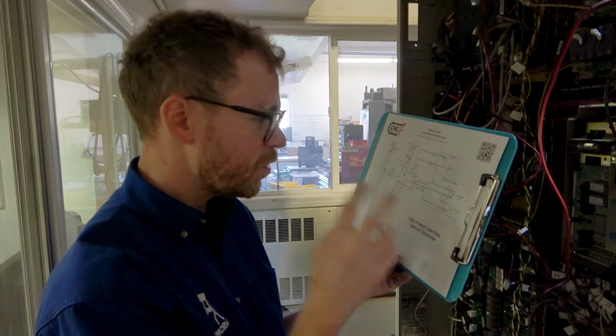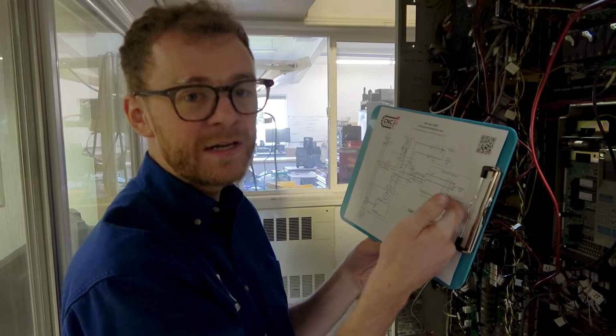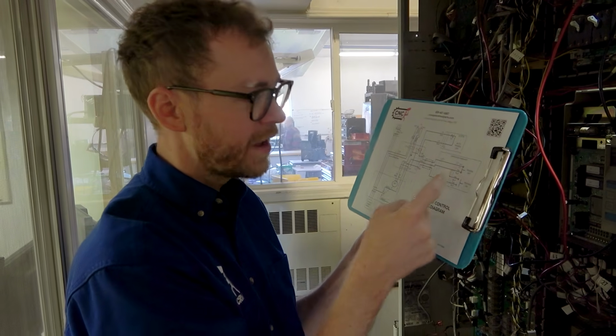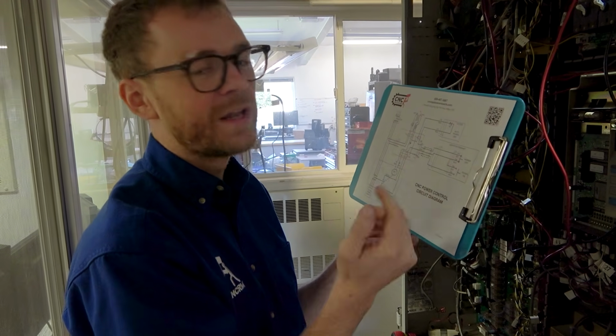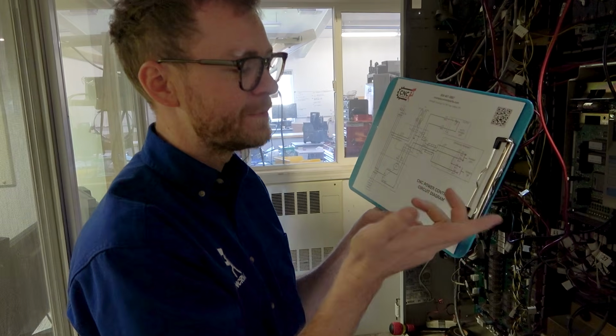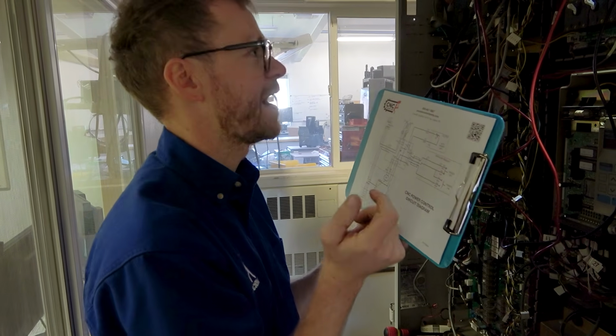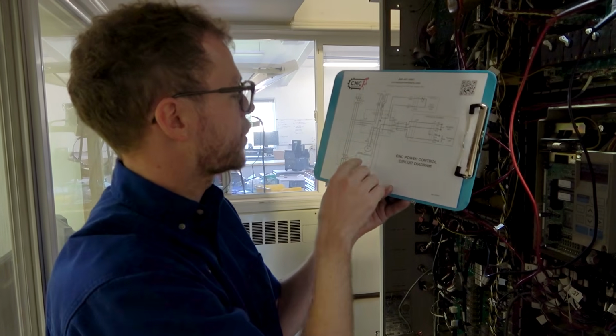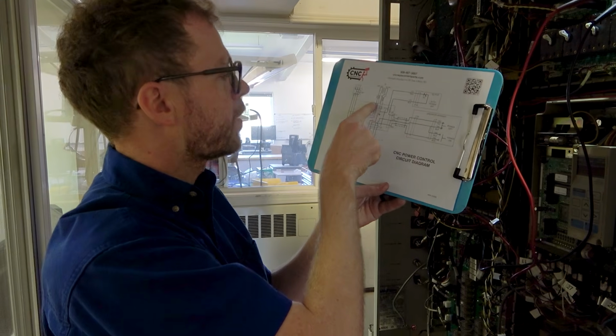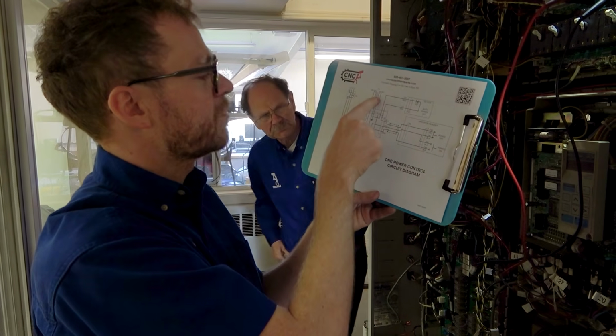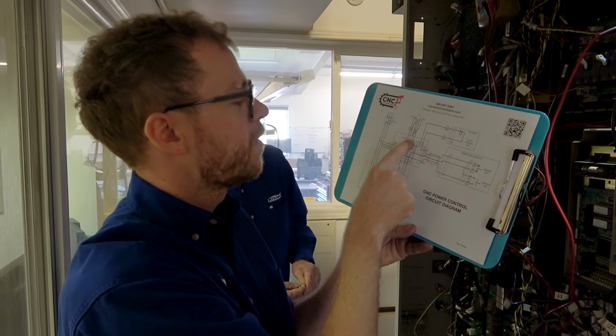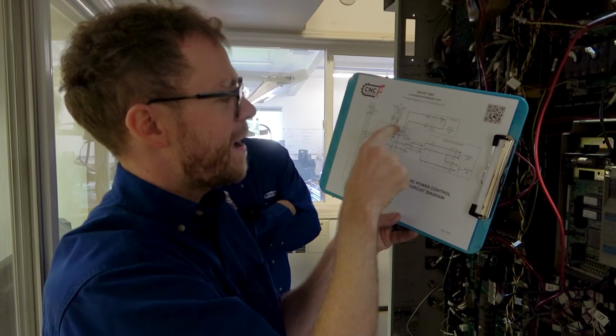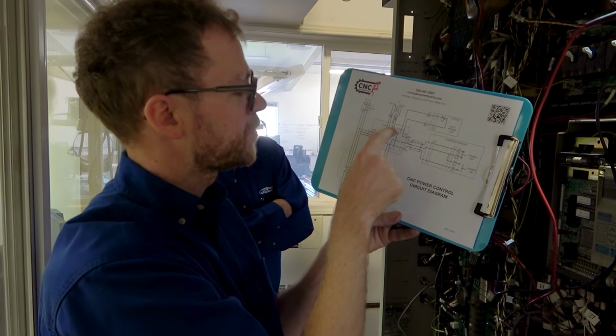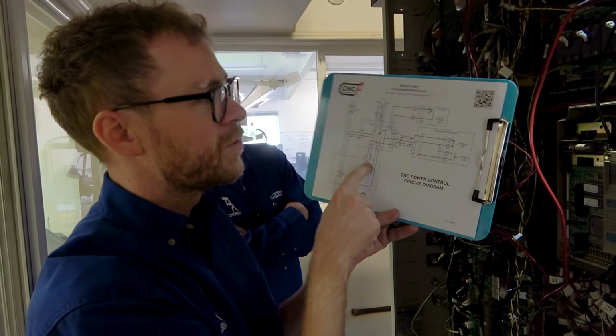But you've got to know this circuit really well to cut it in half, and I want to work my way through the circuit. When this works correctly, the on button turns the machine on and it stays on, and the off button turns it off. It's called a latching circuit. The on button turns it on and keeps it latched. The off button breaks the latch. We're right here in our circuit. We've measured the power going to the transformer, and we're measuring the power coming off the transformer. We have 24 volts. That power comes back onto the power distribution card, goes over and goes to the coil.